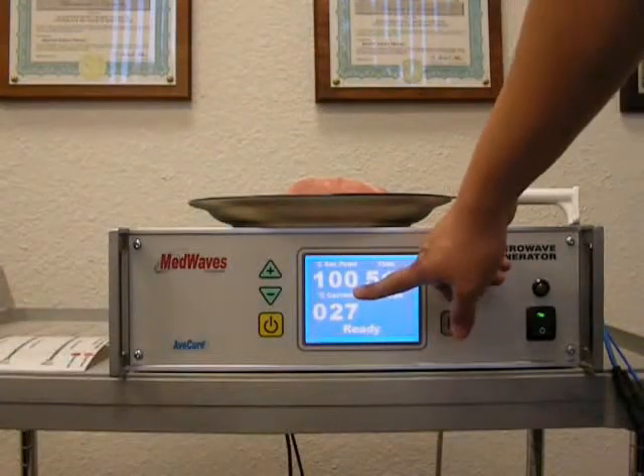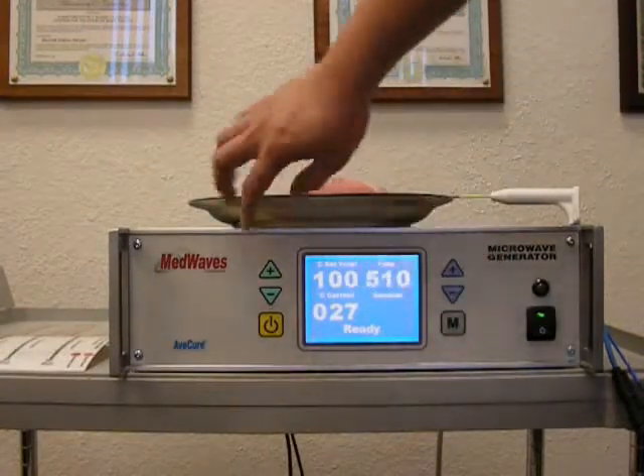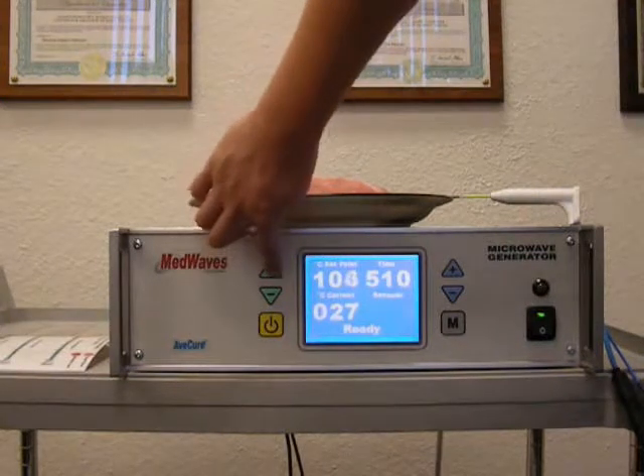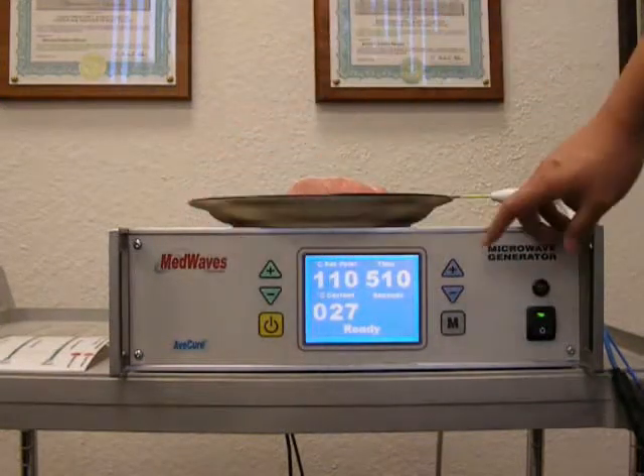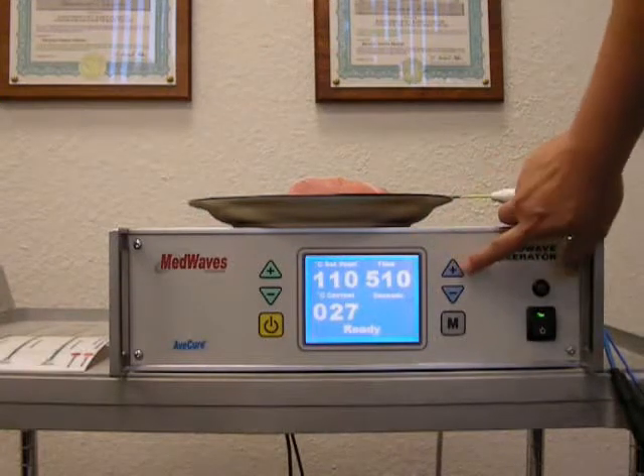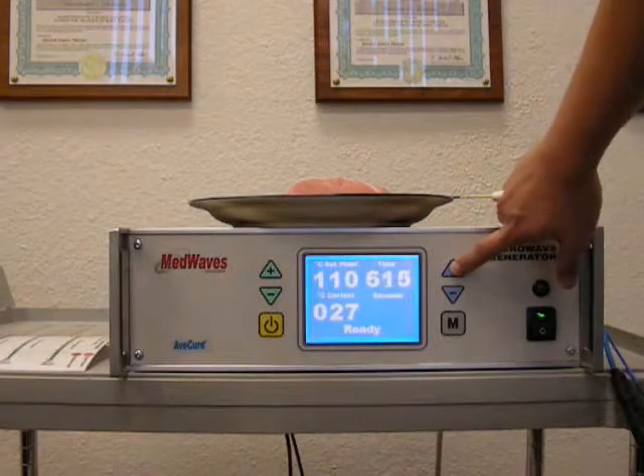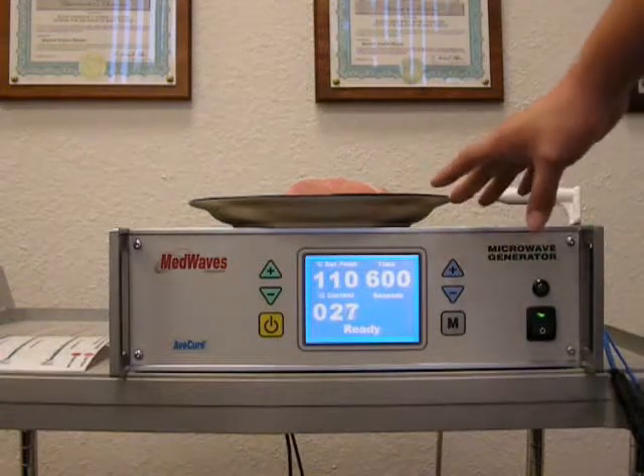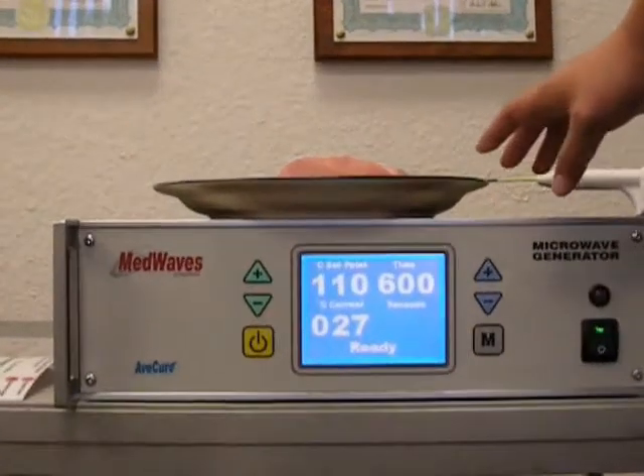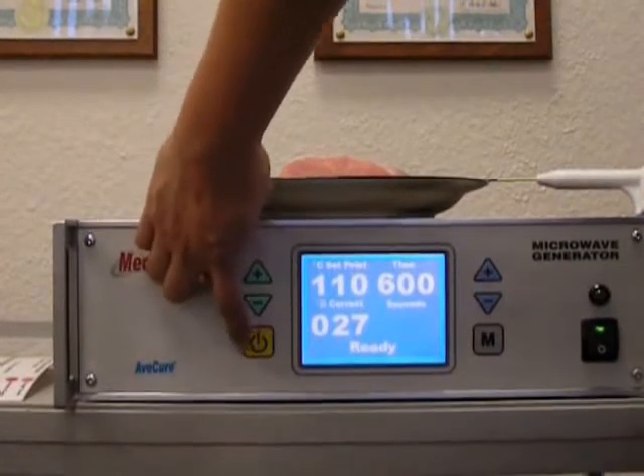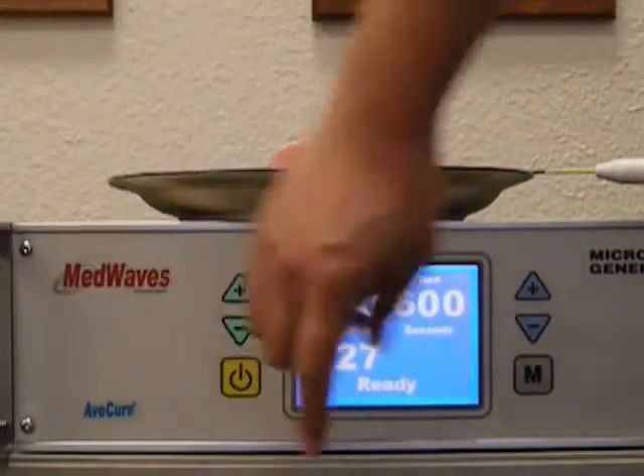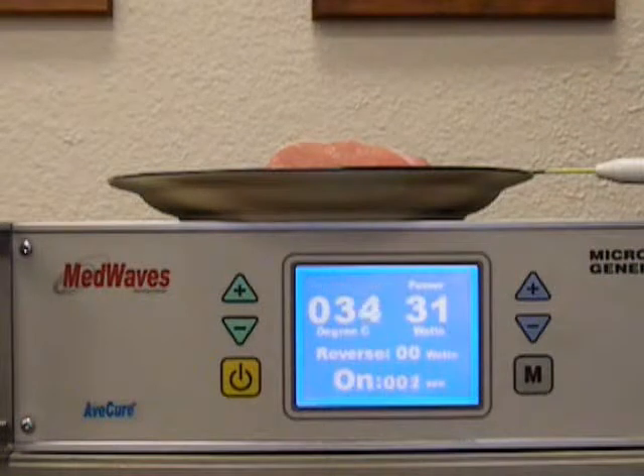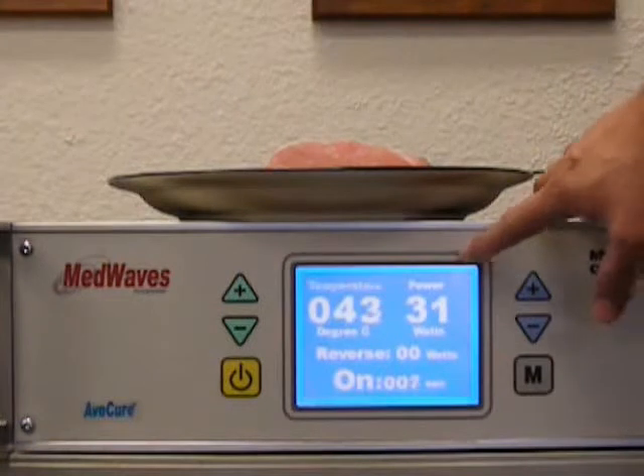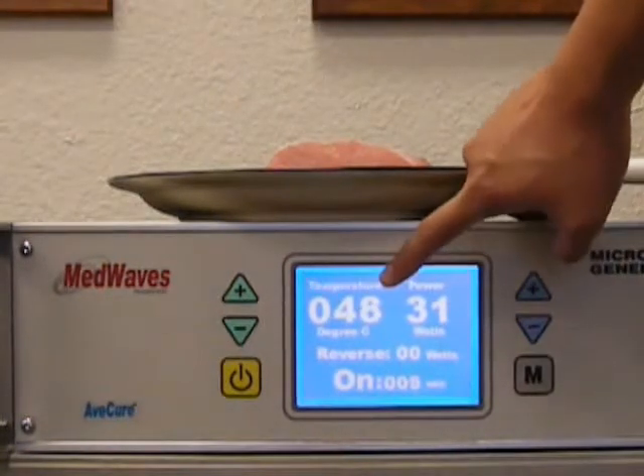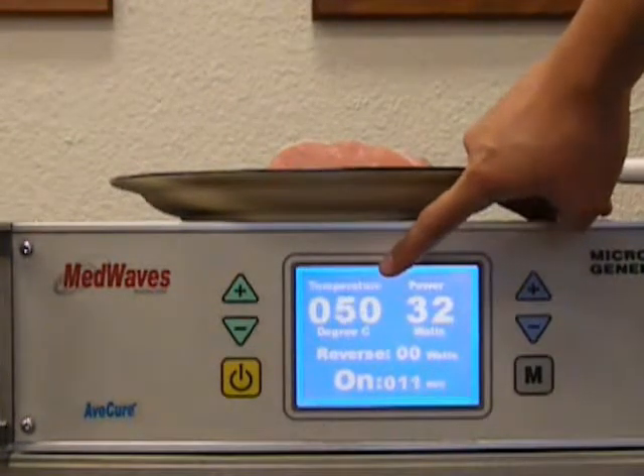The temperature setting is at 100 degrees, but we want it at 110. So I will bring it up to 110. And for the time, we wanted 10 minutes, so I will bring this to 600 seconds. Once the settings are in place and the probe is in the tissue, start the ablation using the yellow button. In temperature control mode, the generator will apply full power until the target temperature of 110 degrees is reached.